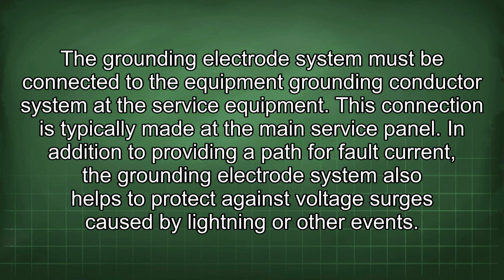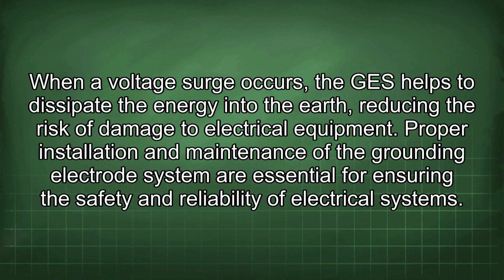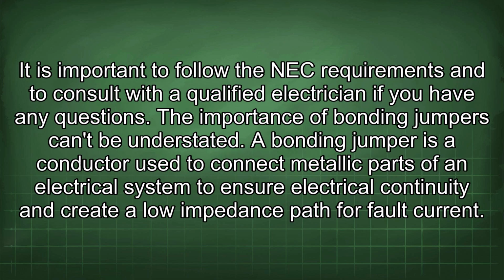In addition to providing a path for fault current, the grounding electrode system also helps to protect against voltage surges caused by lightning or other events. When a voltage surge occurs, the GES helps to dissipate the energy into the earth, reducing the risk of damage to electrical equipment. Proper installation and maintenance of the grounding electrode system are essential for ensuring the safety and reliability of electrical systems. It is important to follow the NEC requirements and to consult with a qualified electrician if you have any questions. The importance of bonding jumpers can't be understated.